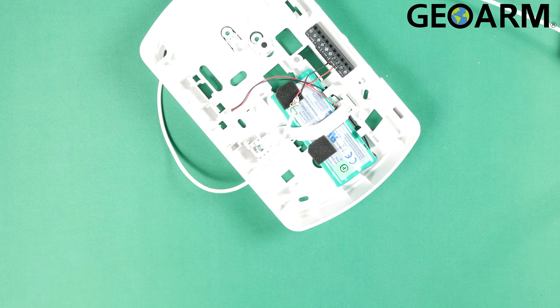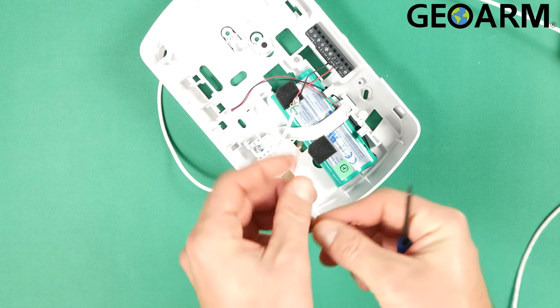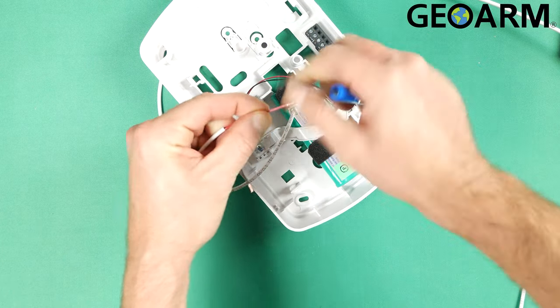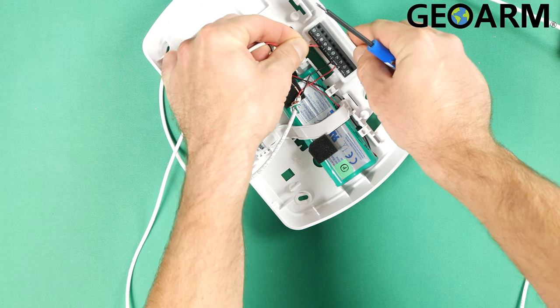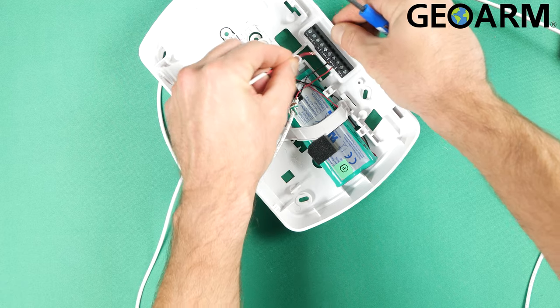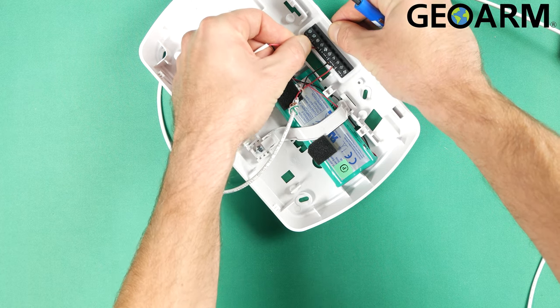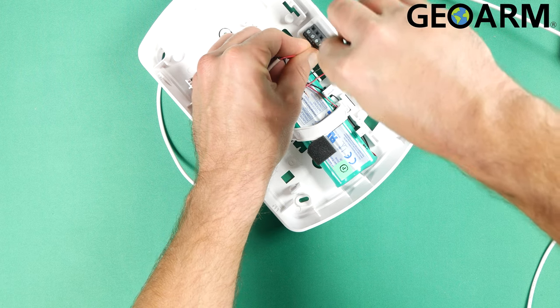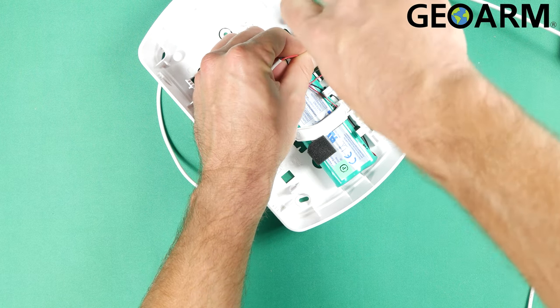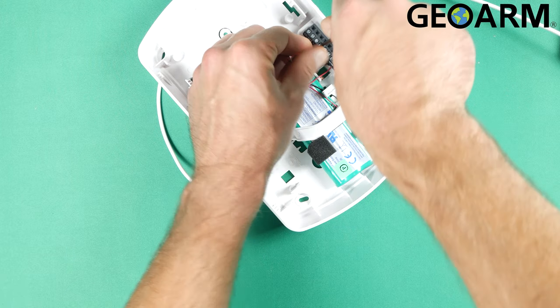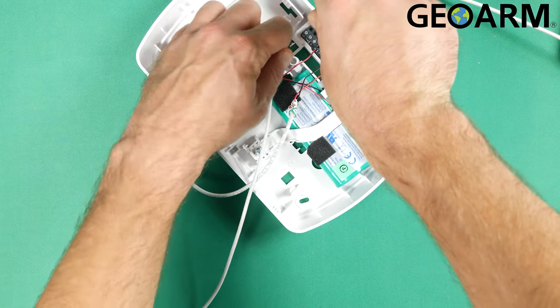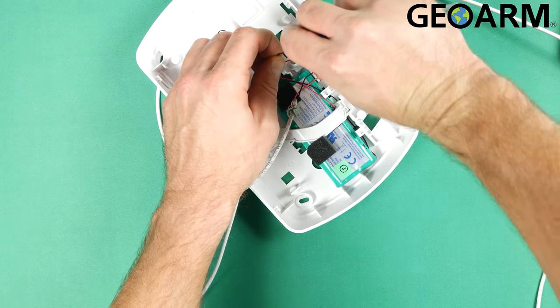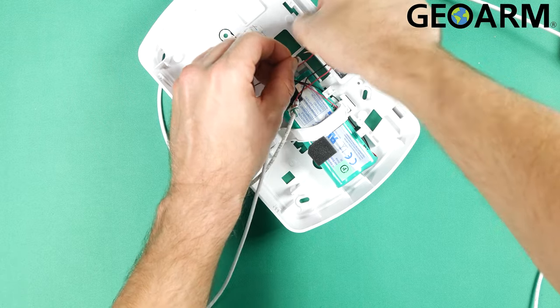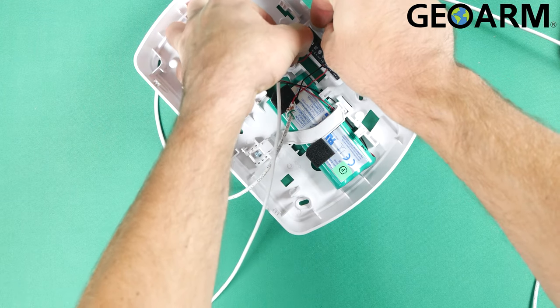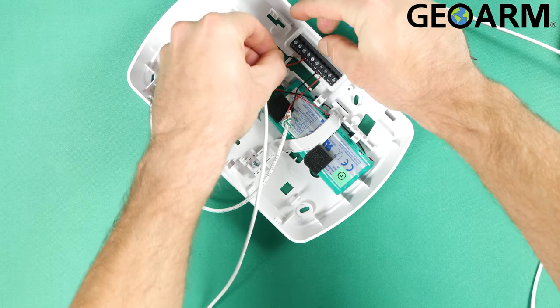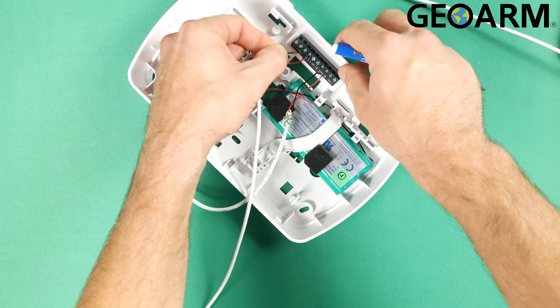So once you get that, go ahead and you're going to be wiring the red wire into ring or R. And remember, you're probably going to want to be pulling these out of like a punch out or through the back of the back plate or something like that, so that way these wires aren't in the way when you go to close your cover. I'm only just showing you this way for quick wiring, but yeah, you want to pull it through the back on this one. All right, so now we're going to go with our black wire to tip. You've made that connection in there, go ahead and tighten it down.